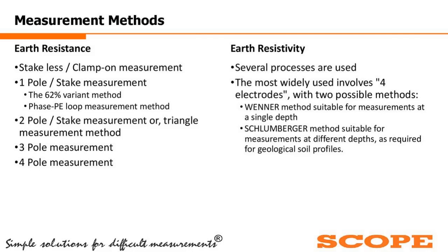These are the two methods available under single pole or single stake measurement. Then comes the two pole or two stake measurement, or triangular measurement method. Then comes the most popular three pole and four pole measurements for the earth electrode or the earth pit resistance measurement. Then coming to the soil earth resistivity, there also, like earth resistance or earth pit resistance measurement, several processes are used, but the most widely used are the four electrode method with two options. One is Wenner's method and the second one is the Schlumberger method. So these are the most commonly used methods.